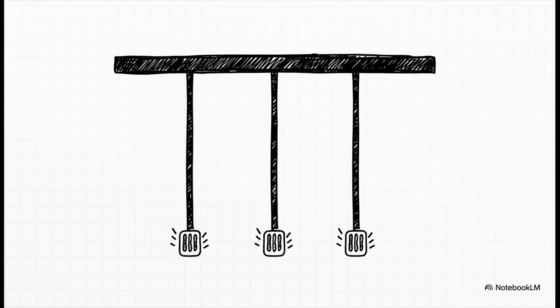And here's a really crucial safety detail that goes along with that. The feeder, that's the main line supplying power to all these heaters, has to be rated for the total load, but it also can't be smaller than the largest single-branch circuit it's feeding. Think about it. If you have one really big heater on its own circuit, the main feeder has to be tough enough to handle that one unit all by itself, no matter what else is going on. It's another layer of safety.